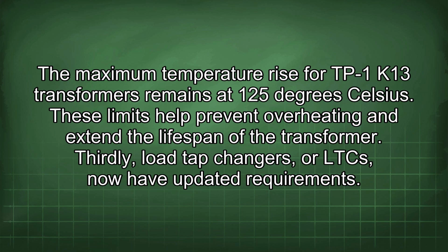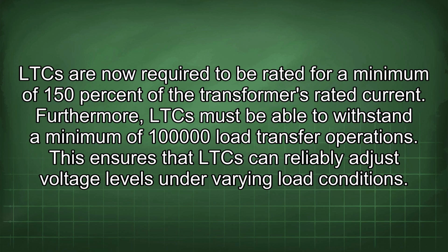Thirdly, load tap changers, or LTCs, now have updated requirements. LTCs are now required to be rated for a minimum of 150% of the transformer's rated current. Furthermore, LTCs must be able to withstand a minimum of 100,000 load transfer operations. This ensures that LTCs can reliably adjust voltage levels under varying load conditions.